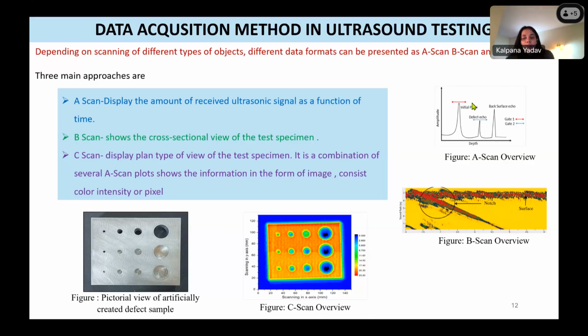But while you are doing a B scan, it's a linear scan. You can say it's a line scan. You move your transducer along the length of the specimen, and it gives you a cross-sectional view of the test specimen. If you see here in the figure, I was talking about what is going to be reflected from your sample. The signal is going to look like this in the A scan overview. It's going to be amplitude versus depth, or amplitude versus time. The initial pulse is from the surface of the sample, and if there is any defect in between in the sample, you're going to receive that defect echo. And from the back surface, you're going to have a back surface echo. And you have gate settings. The gate is going to capture whatever you want to capture. For example, I want to know the time of the initial pulse, so I'm going to set my gate at the initial pulse.